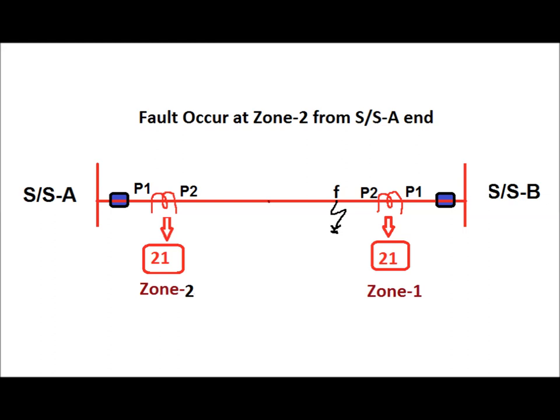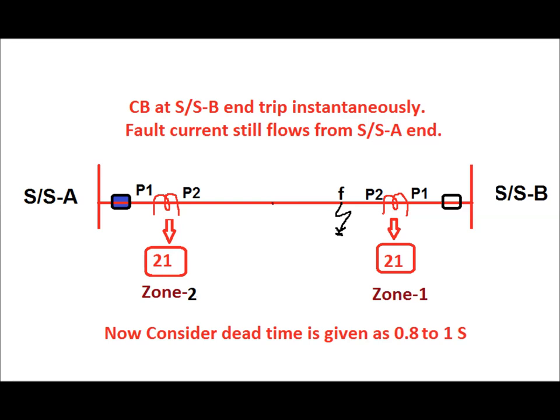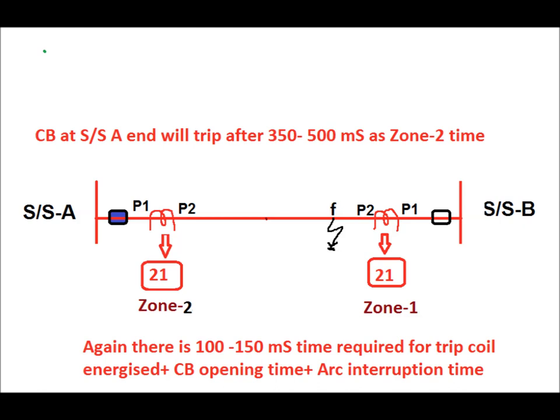Now consider a fault at Zone 2 location from substation A end, which is simultaneously at Zone 1 location from substation B end. Since the fault is in Zone 1 from substation B, the relay at B trips instantaneously without any time delay. At substation A end, the relay waits 350 to 500 milliseconds before sending a trip signal, plus another 100 to 150 milliseconds for trip coil energization, CB opening time, and arc interruption time — so approximately 500 milliseconds total to clear the fault from substation A end.